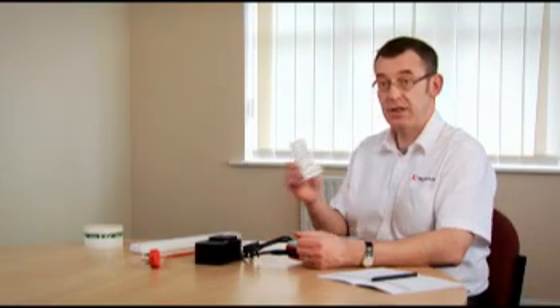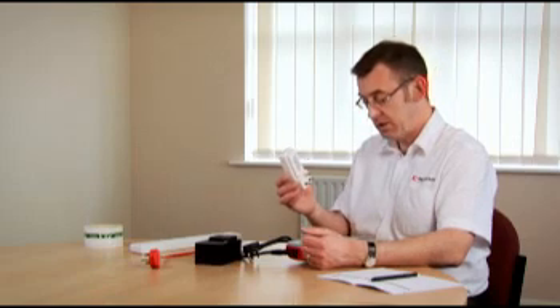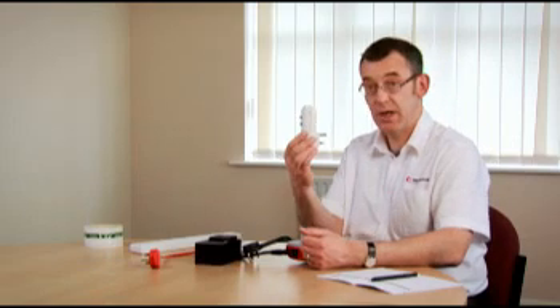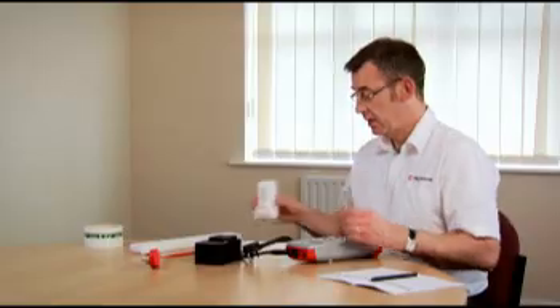Now we're going to test this plug-in RCD. We can use the test instrument to measure the trip time or the trip speed of the RCD. To do the test, the RCD needs to be connected to a mains outlet. If, however, we were to connect the RCD directly to a mains supply, there is a risk that we will trip the RCD in the main supply into the building.